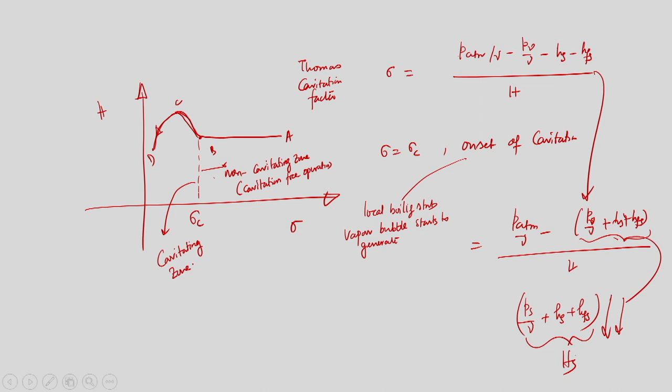We should be very serious about this unwanted phenomenon whenever we are designing a pumping system. There are two suggestions. First, we should always go for flooded suction mode, that is, the impeller axis should always be below the water level in the sump, so that apart from the atmospheric head, we have another head corresponding to the static height. If we run the pump in flooded suction mode, we are always safe from this unwanted phenomenon.